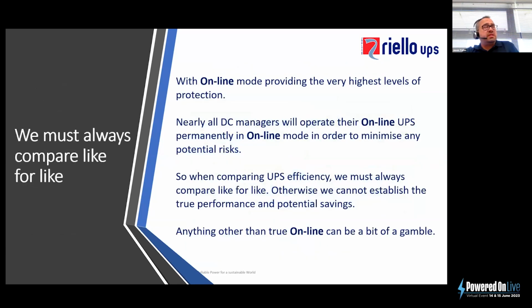Now, I can say with certainty that most online UPS systems will provide you the very highest level of protection. Nearly all DC managers will typically operate their online UPS systems permanently in online mode in order to minimize any potential risks to the data center. So what I'm saying here is that when comparing UPS efficiency, we must always compare like for like. Otherwise, we cannot establish a true performance of the potential savings that could be gained by upgrading UPS systems.